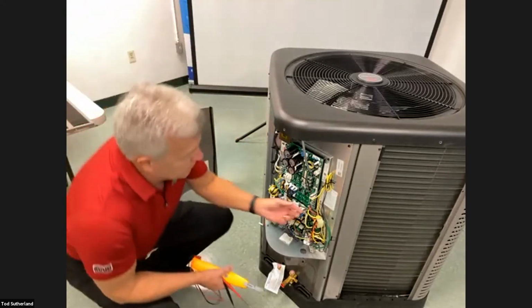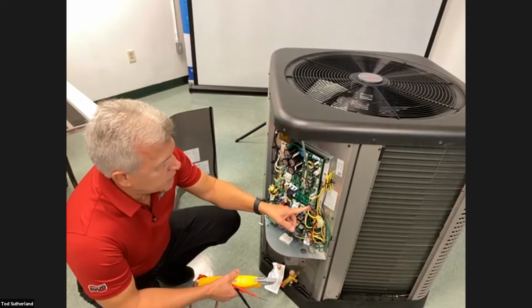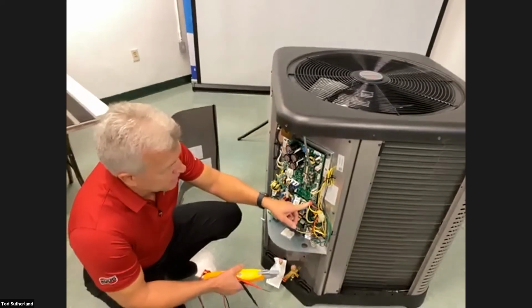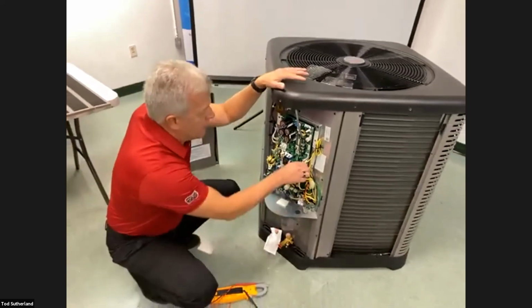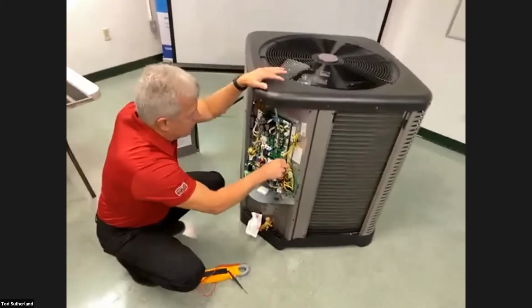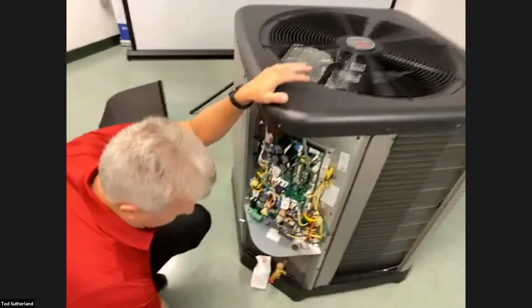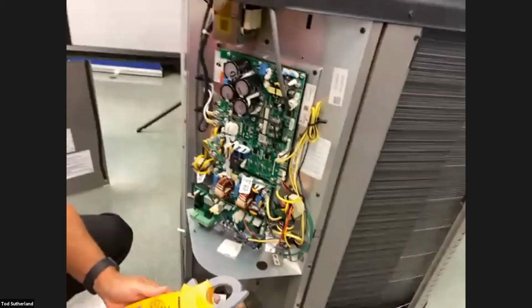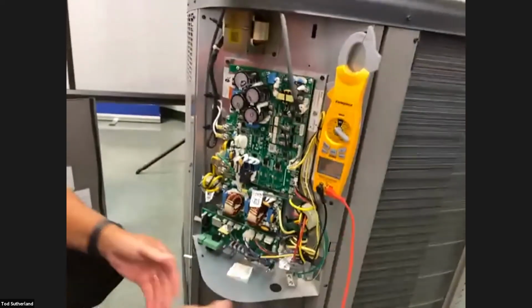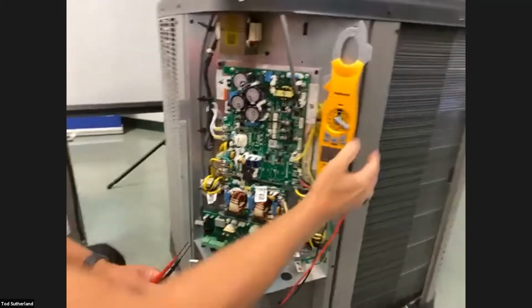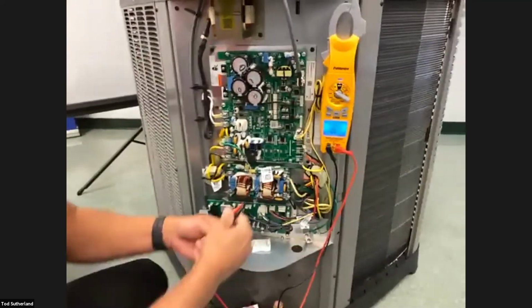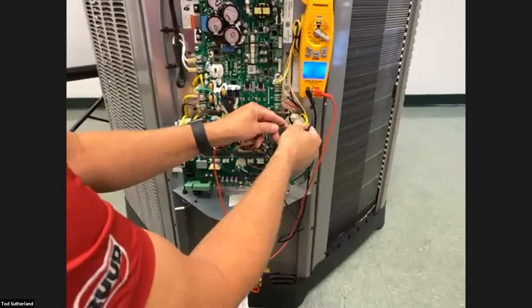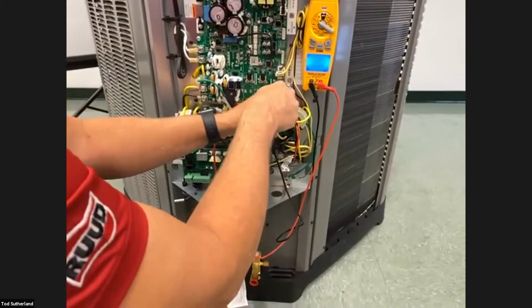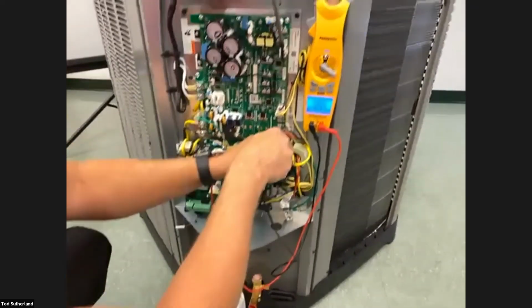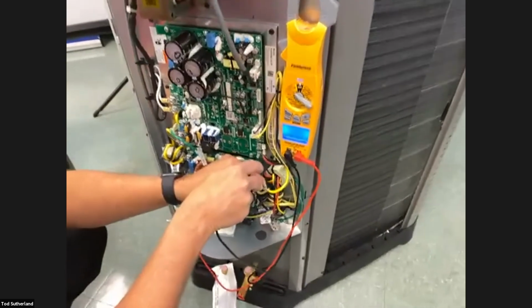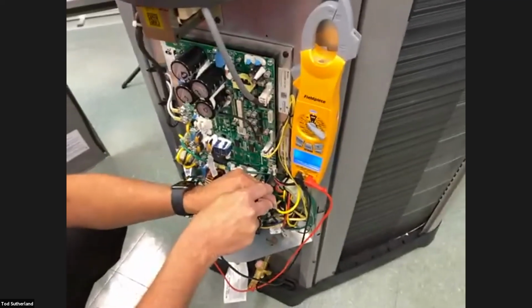These are your compressor terminals down here, your U, your V, and your W. These go out to your compressor. So if you need to ohm out the compressor, you're simply going to pull these off of here. You're going to put your meter to the ohm scale, and you're just going to ohm out each one to itself. And they should all be about the same.